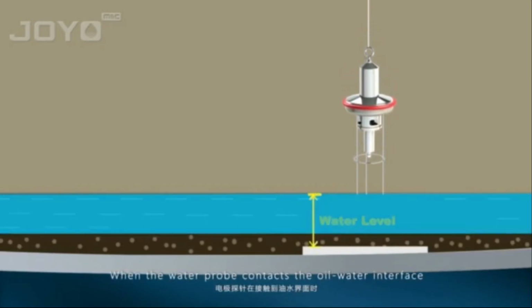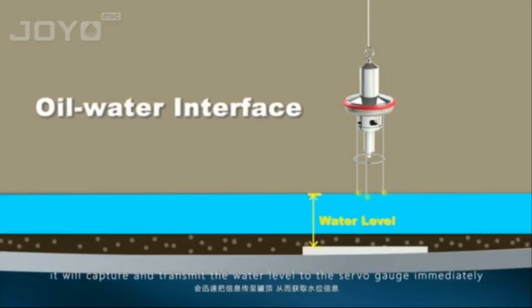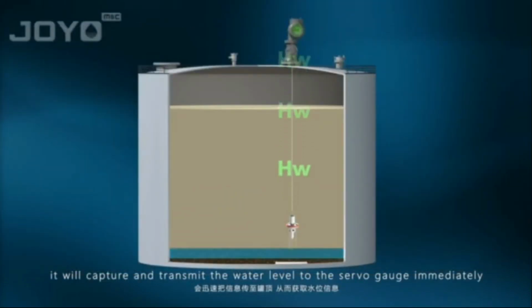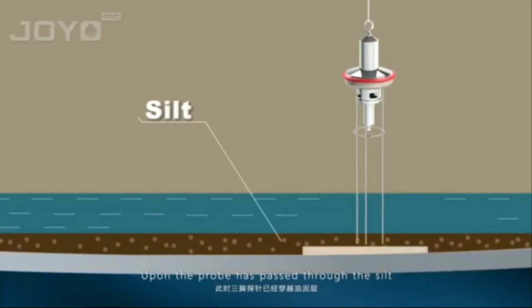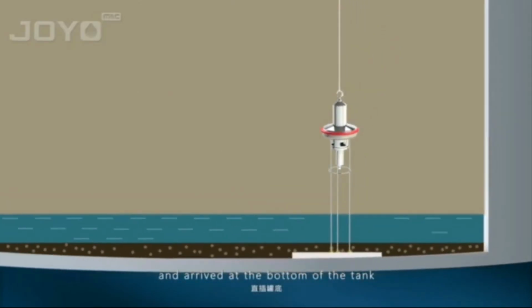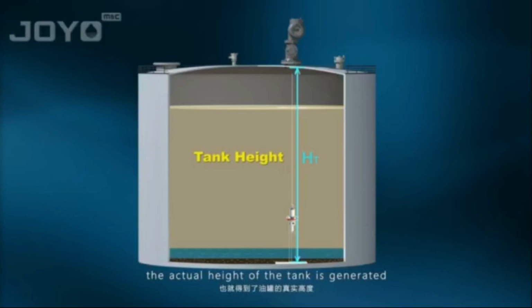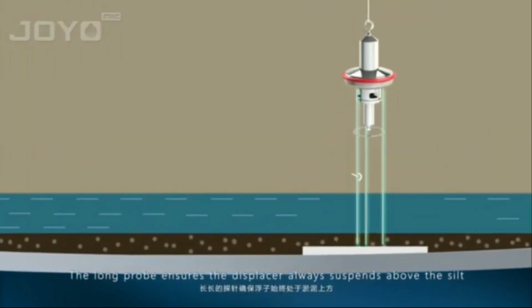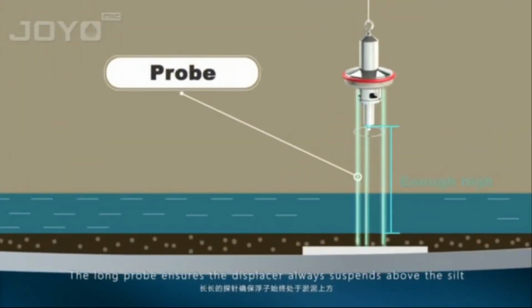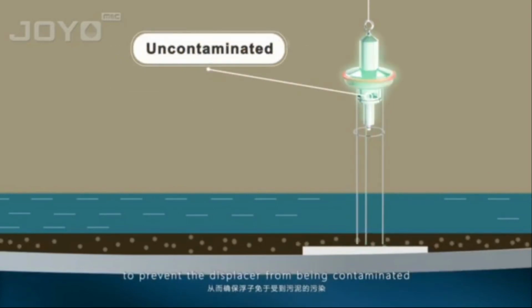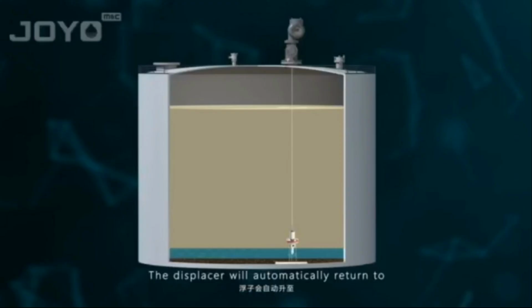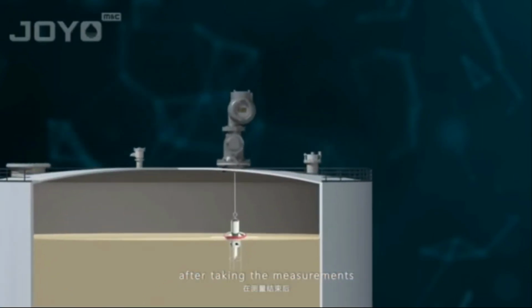When the water probe contacts the oil-water interface, it will capture and transmit the water level to the servo gauge immediately. Once the probe has passed through the silt and arrived at the bottom of the tank, the actual height of the tank is generated. The long probe ensures the displacer always suspends above the silt to prevent the displacer from being contaminated. The displacer will automatically return to and keep floating on the surface of the product after taking the measurements.